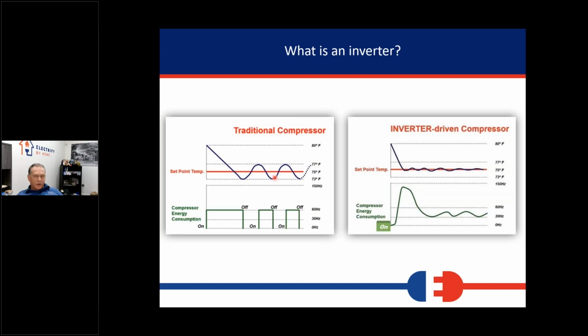So the inverter-driven compressors are a little bit different. That inverter part of it actually takes the power from the wall and converts it to a different source of power inside the unit. It inverts it to like a hybrid 3-phase power. That allows it to operate out of the normal 60 hertz power range.